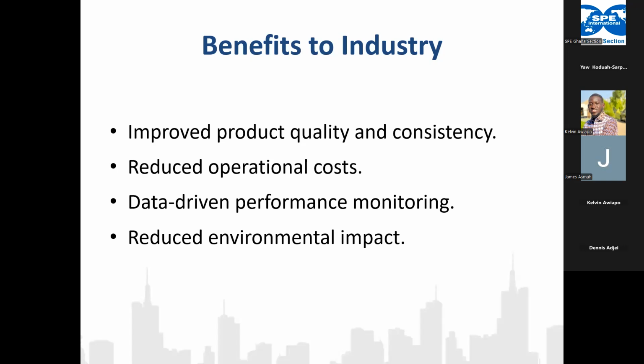We also have data-driven performance monitoring. For every industry, we have KPIs or key performance indicators. Based on the data that you have, because process control is able to keep an archive of all the readings on the various transmitters, you can, at any point in time, have a summary of what you've done so far, how each of them is going, and the failure rate of a particular brand of transmitter.